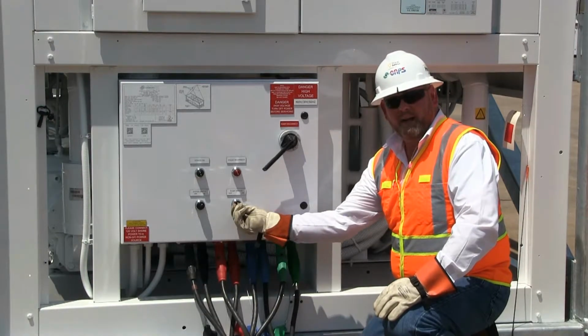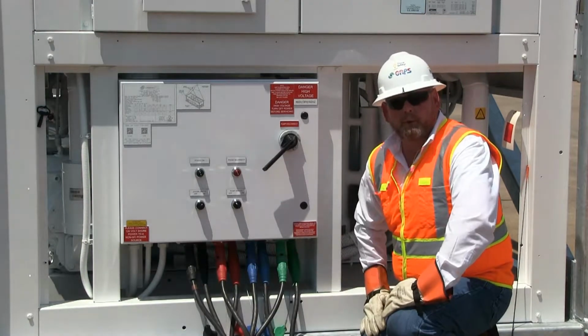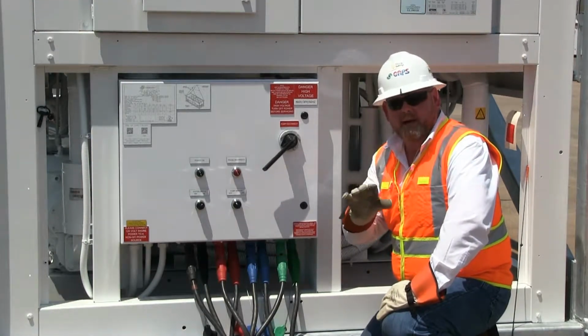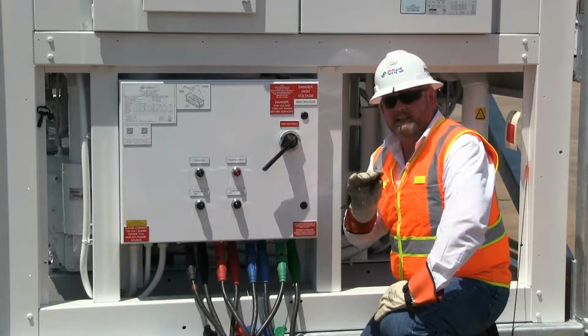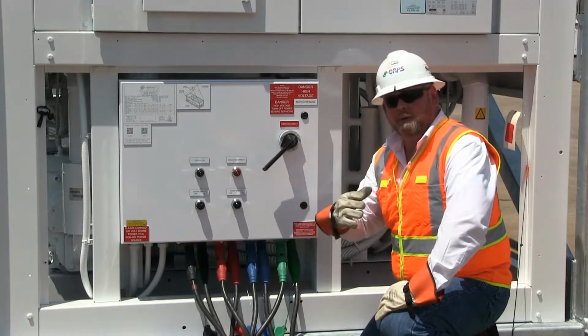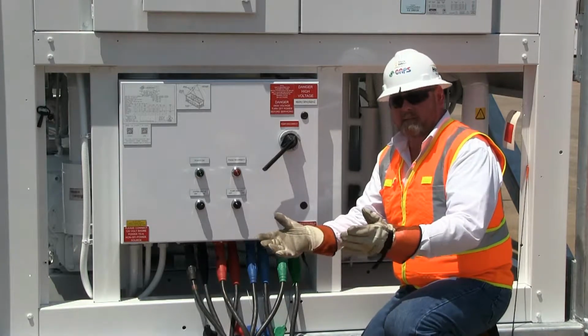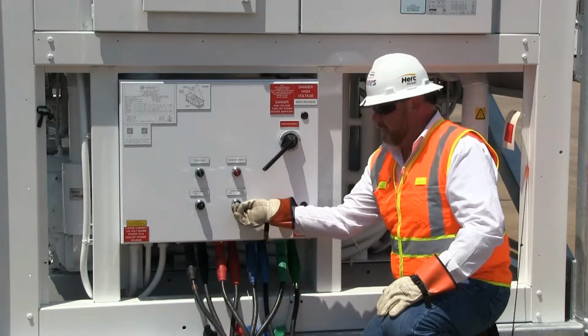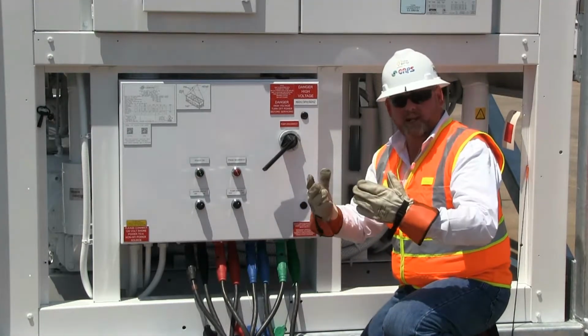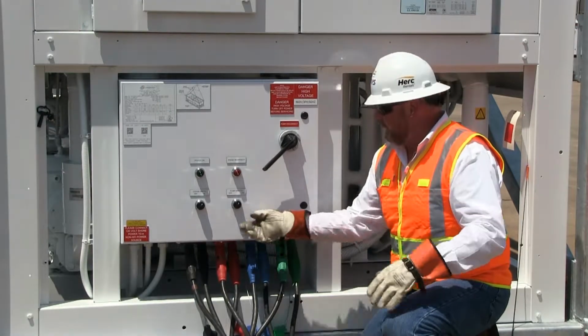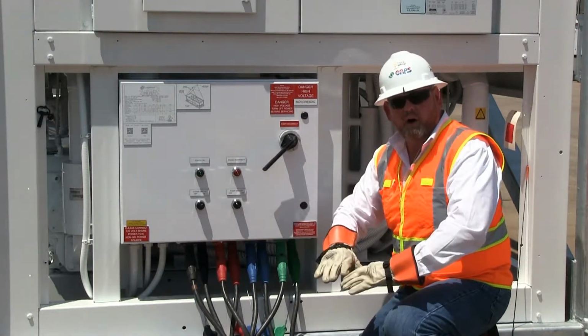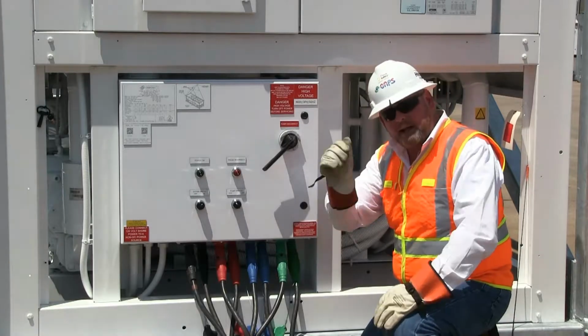Back on and off. Now what you want to remember is you can never get the air out of the system as long as the pump is running. So you want to go through a cycle as you're filling the system and going to your high points. You'll want to turn that on for 3 or 4 seconds, stir the water up. Then when you turn it off, all the water will fall, all the air will go up, and that'll allow you to bleed the air off of the system.